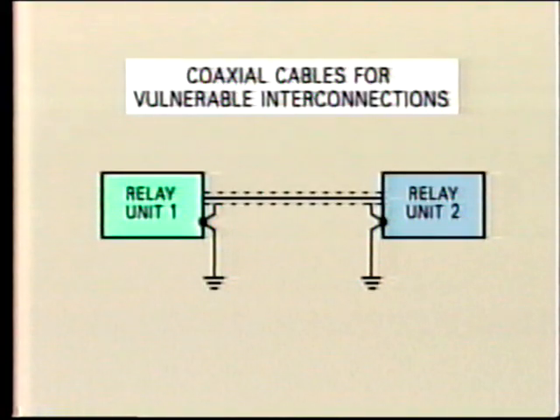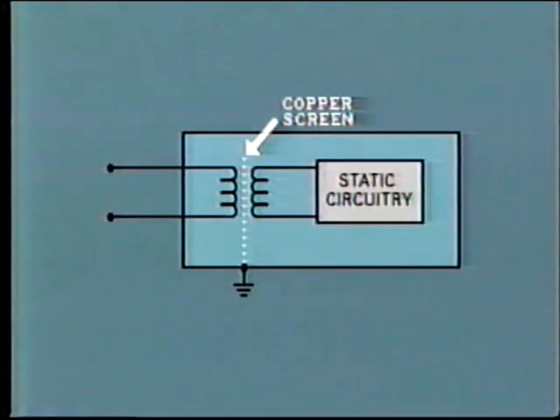Input leads to the relay should be shielded or screened and grounded so as to prevent interference. Care must be taken when grounding screens so as to prevent the possibility of ground fault current flowing through the screen and destroying the cable. You will remember that we discussed the problem in earlier tapes. In some circuits, transformers are fitted with a grounded copper screen between the windings. This is to prevent the transfer of interference signals across the transformer.